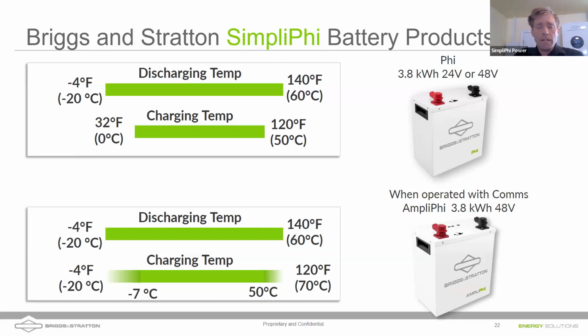On our more advanced batteries with communicating BMS units inside, these batteries are able to charge even below 0 Celsius. They can charge all the way down to -20 Celsius, but at a greatly reduced rate, and they slow that charging rate down. As that battery heats up with the charge cycle, we can increase that rate.